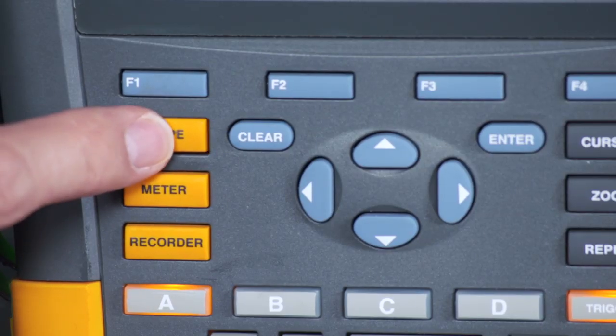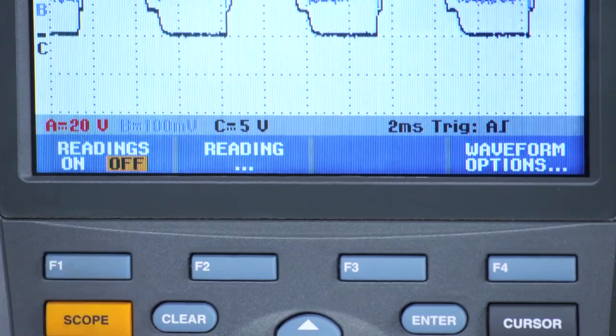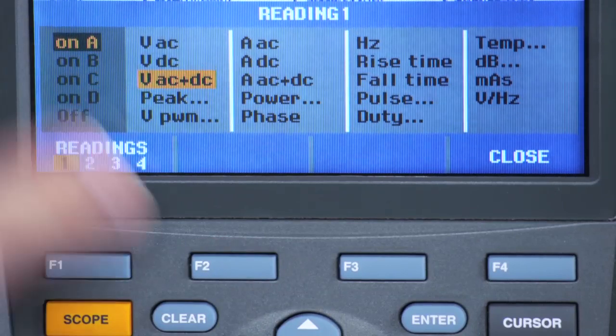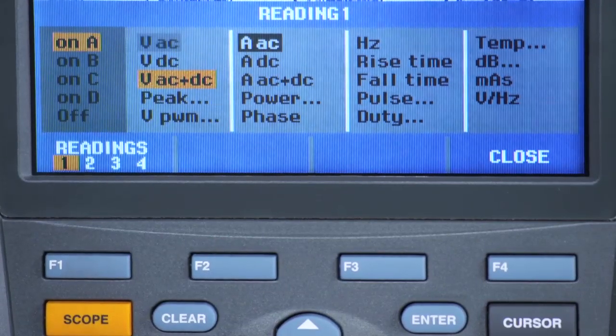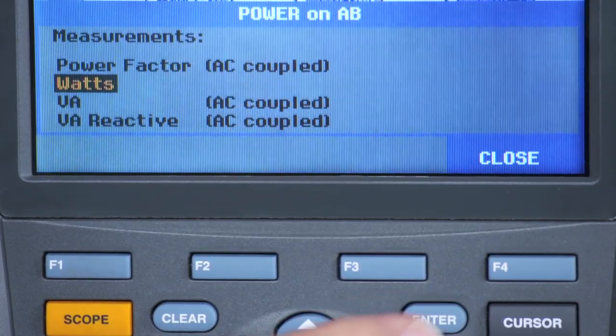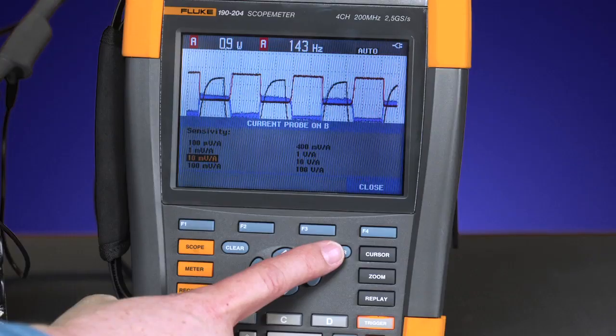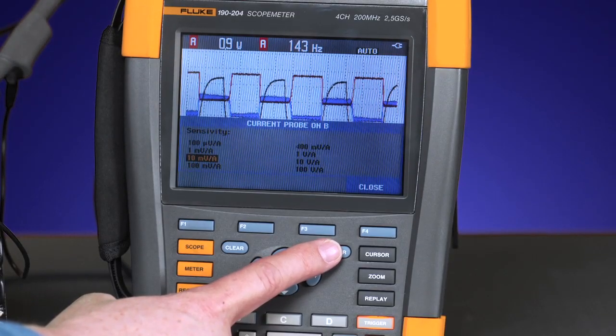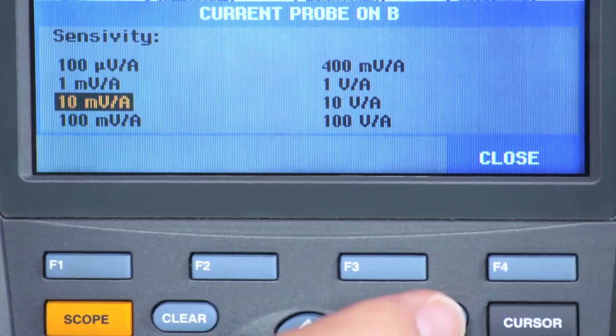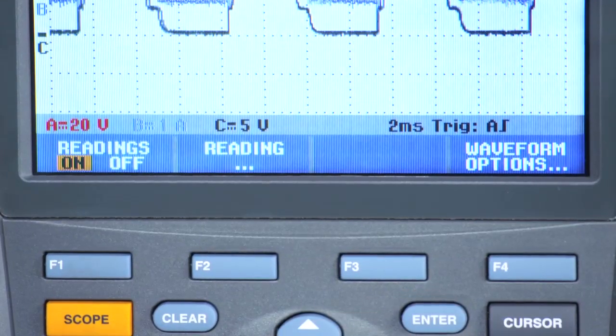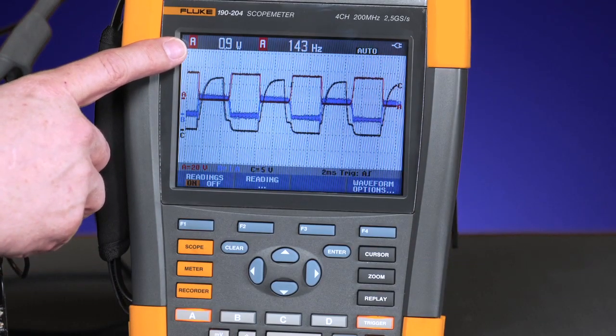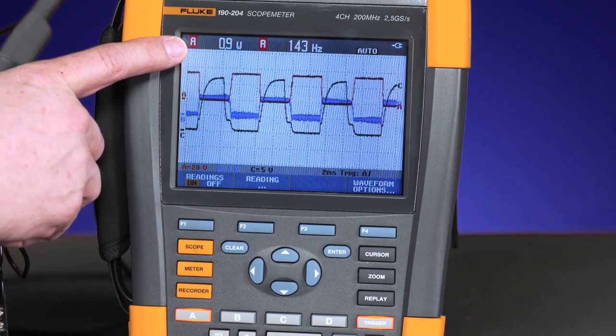Press the scope button, readings on, then choose reading one to measure power across A and B. Selecting Watts mode will give you the unit of measure you need. Scale the sensitivity on the input probe to 10 millivolts per amp or whatever the current probe you have selected. Once you've stepped through those key presses, you can see input A or measurement A. You're measuring the power in watts across the fast switch.